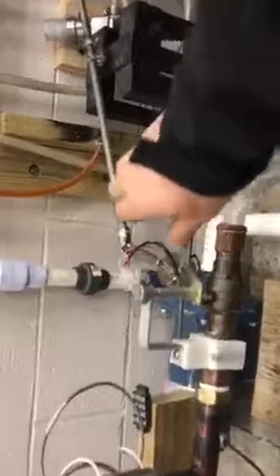So I'm going to hit record, and I'm going to generate the water hammer in the system. Now it's recording, so I will make sure of it. As you can see here, I will go and close the valve very quickly, and I think you can hear the sounds, and you see how it's jumping. So it generates water hammer in the system, and this one is ranging, but the upstream seems like not the case. However, let's see the signal. I'm going to stop it.